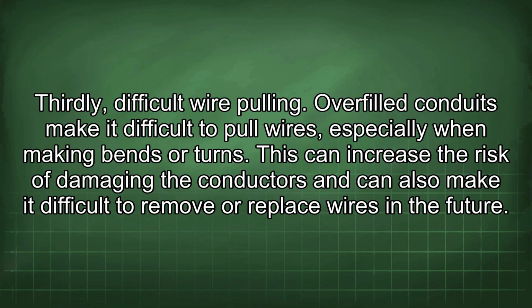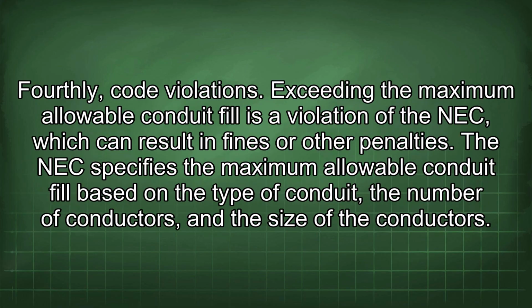Overfilled conduits make it difficult to pull wires, especially when making bends or turns. This can increase the risk of damaging the conductors and can also make it difficult to remove or replace wires in the future. Fourthly, code violations. Exceeding the maximum allowable conduit fill is a violation of the NEC, which can result in fines or other penalties.